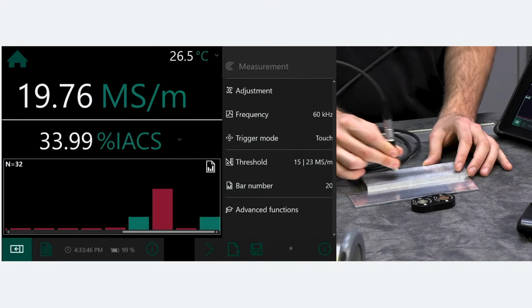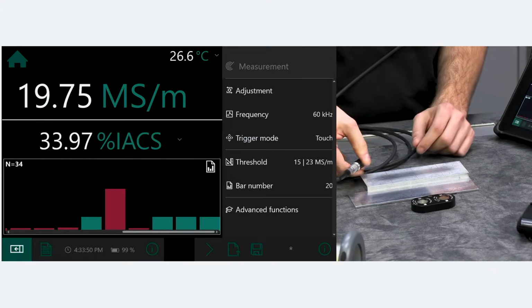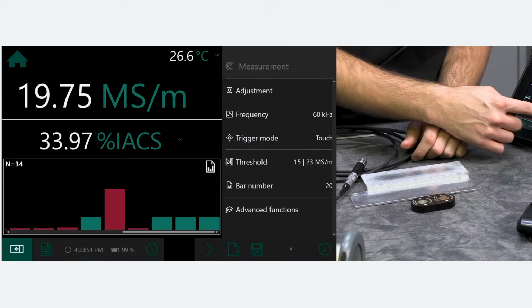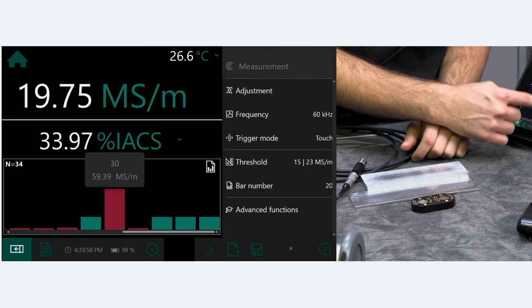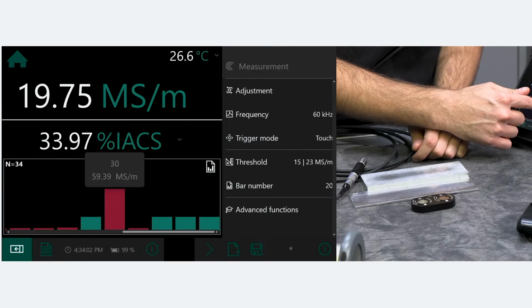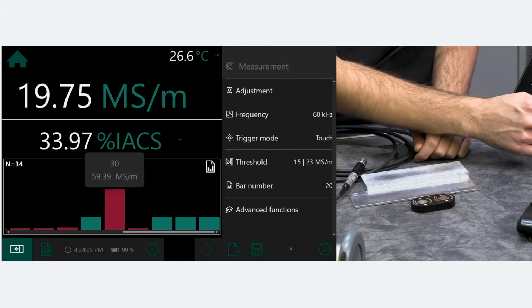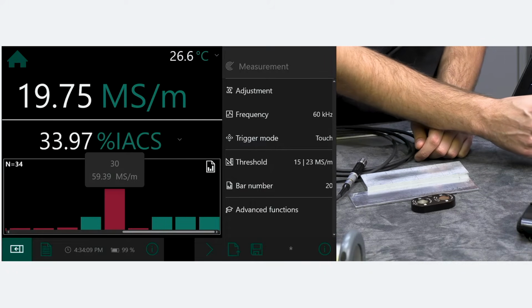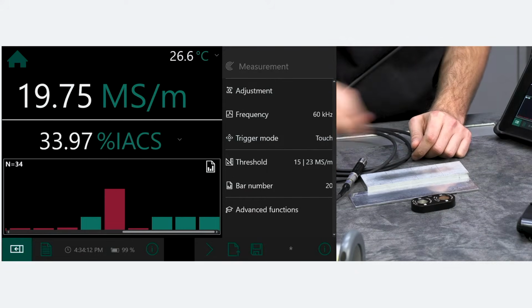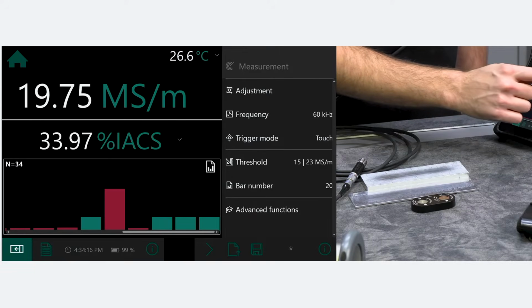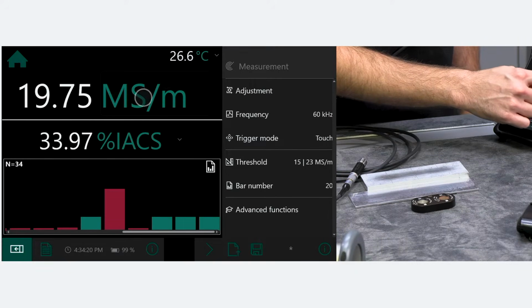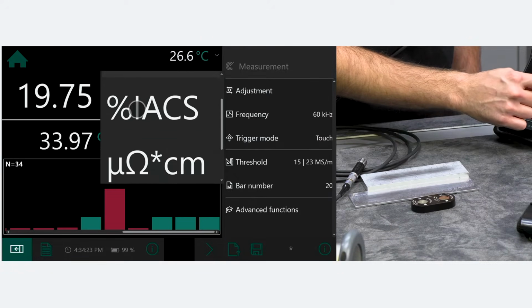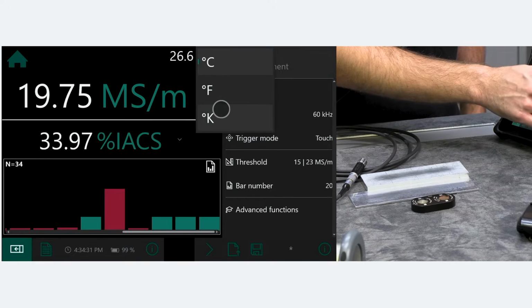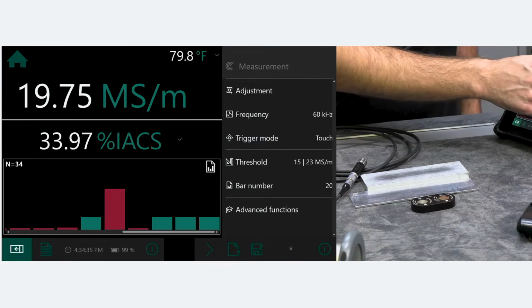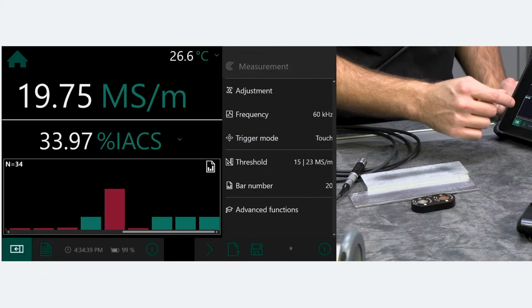And here we can do single measurements on the material and see a bulk. The signal is displayed here, and if we'd like to see, okay, what was, as an example, this red one, we can press on it, and okay, it was the 30s measurement, and it had the value of 59.39. Yeah, I set up a threshold to sort out values above 23 megasiemens per meter, so that's correct. If we'd like to switch to another unit, as an example, instead of megasiemens per meter, percentage IACS, I press on this and I can directly choose between the different units. And always, if I do that, this unit is completely set up in the background, so you don't need to search in some menu to switch these units.